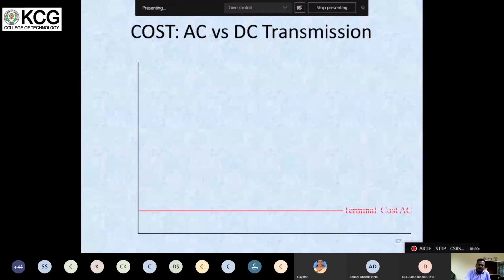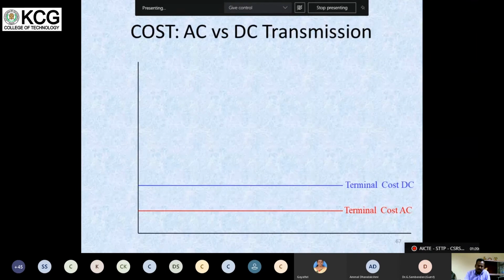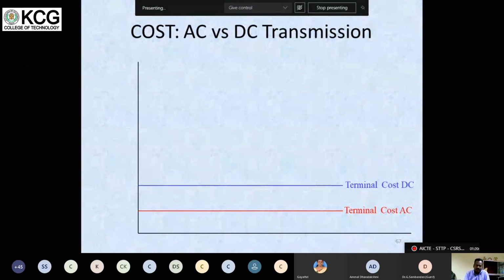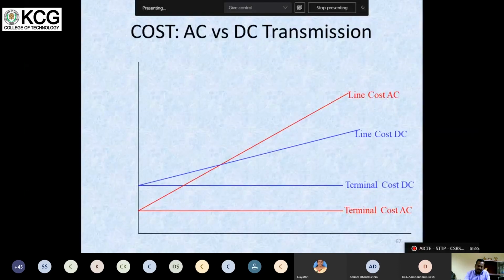You can see here the terminal cost of AC. That is the substation cost of AC. This is the substation cost of DC, because DC means the AC power has to be converted, so inverter stations, receiving and sending ends. Then there is the line cost of AC, then the line cost of DC. Beyond some particular distance, the line cost of DC and the total cost of the transmission system reduces. That distance is called break even.